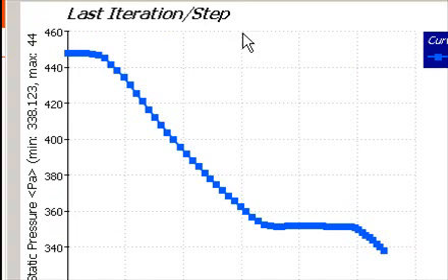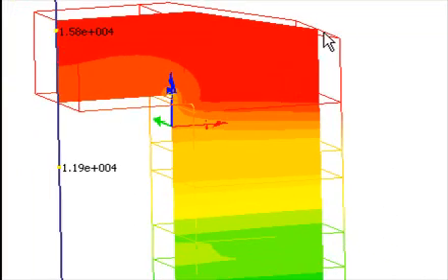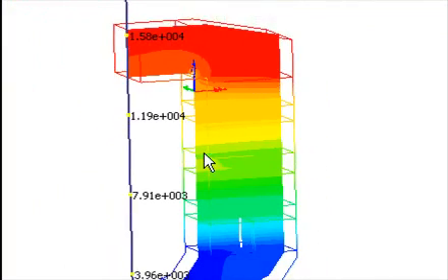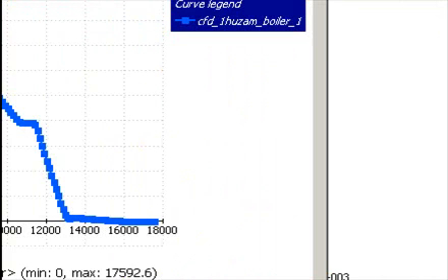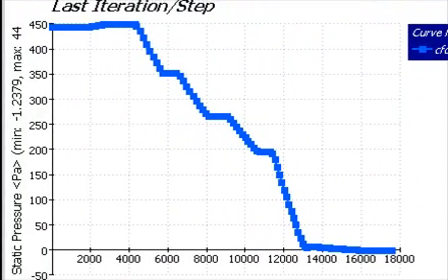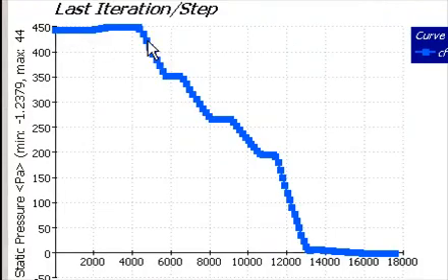The 96 pascals of the superheater is also there, and the resistances of the other two bundles match the results from the 2D calculations. Beside those, the pressure loss of the whole steam generator can be obtained from a graph generated by the CFD code. It is 444 pascals. This is what it's all about.